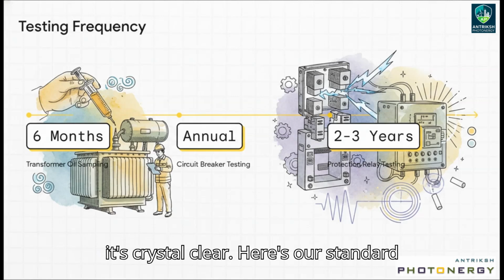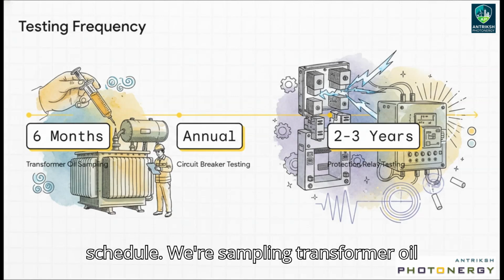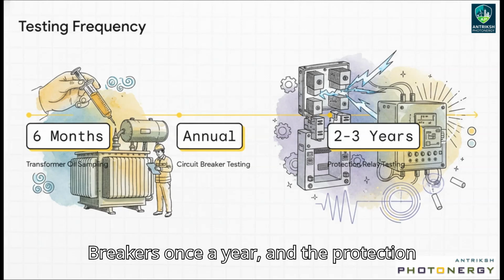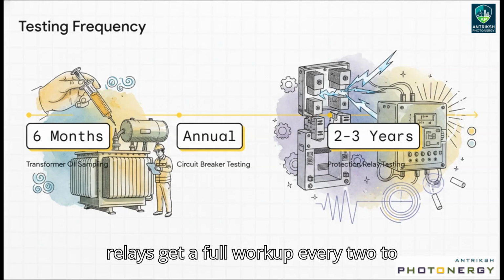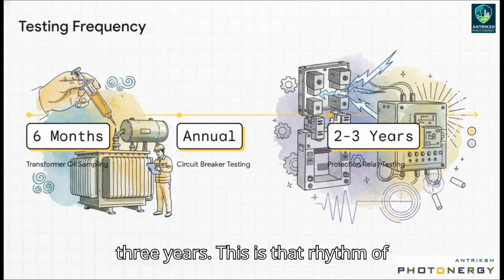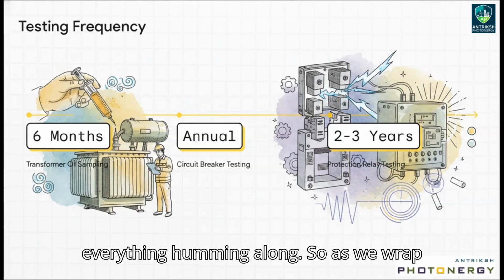And just so it's crystal clear, here's our standard schedule: we're sampling transformer oil every 6 months, testing circuit breakers once a year, and the protection relays get a full workup every 2 to 3 years. This is that rhythm of proactive maintenance that keeps everything humming along.